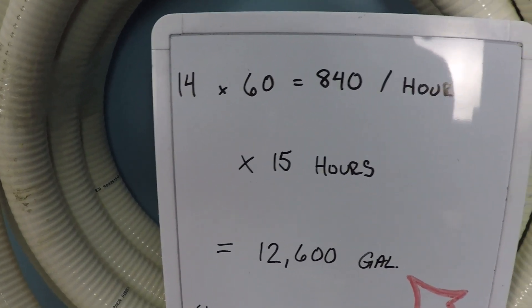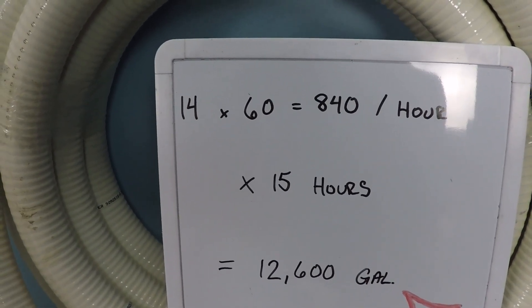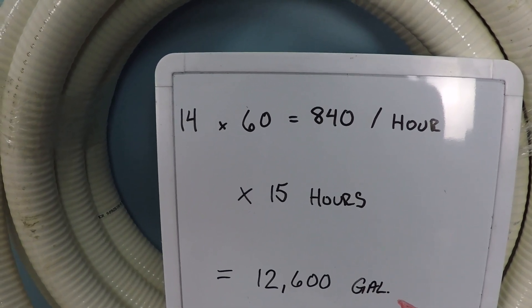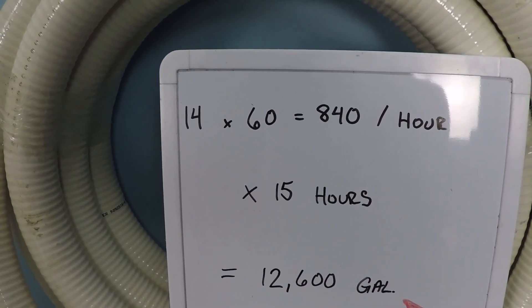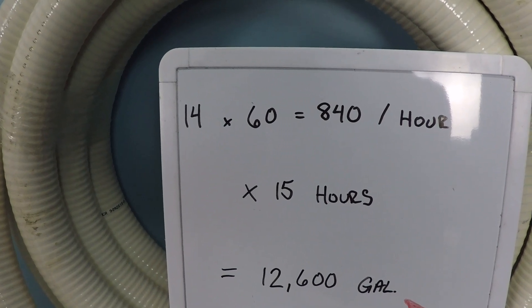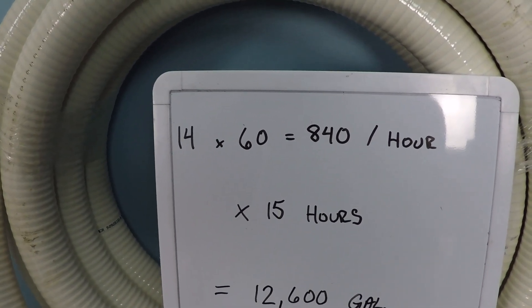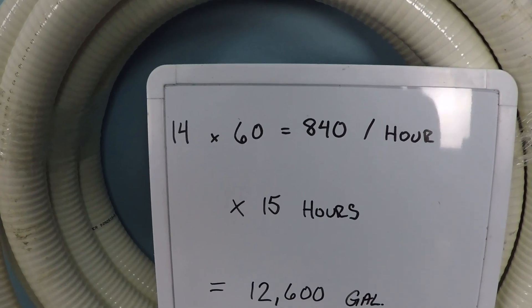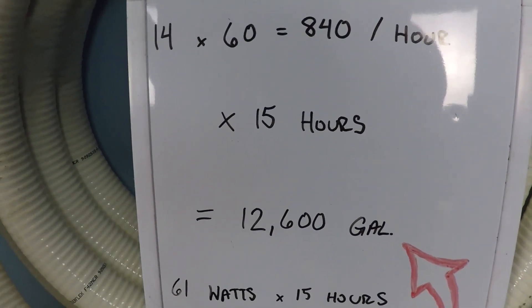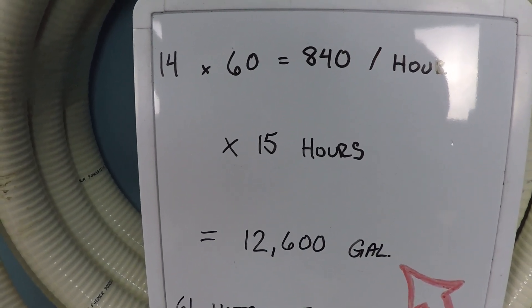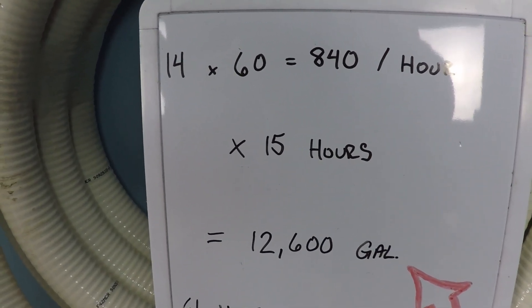I chose 15 hours as a suitably long runtime because you want long hours of low RPM running for a variable speed pump. But your pool and the peripheral items still need periods of time at medium and higher speed operation. 15 hours is a nice long chunk of time because after 15 hours we're able to achieve 12,600 gallons of filtered water.